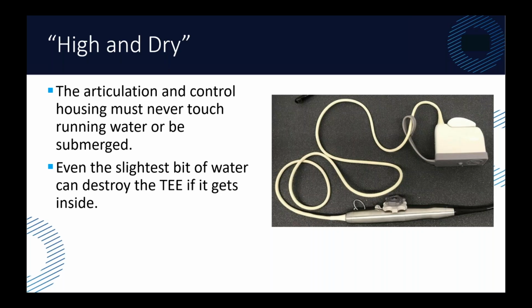Any water that enters into here, this is not waterproof at all. So you can get in through some of the seams in the metal, or you get water into the connector, and then that connector gets held up higher in the probe, that water will make its way all the way to the distal tip of it. And there are electronics in all the connectors, so it'll wreak havoc there as well.